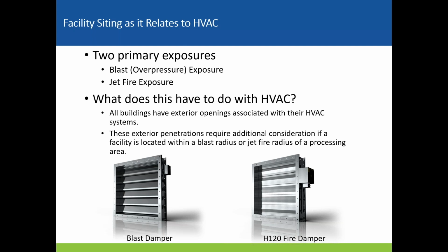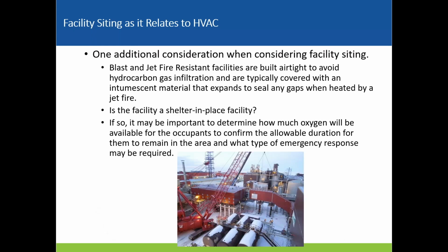So all buildings have exterior openings. And our blast dampers, and each has an H120 fire damper. So that's for a hydrocarbon fire for 120 minutes. That's theoretically what it's rated for. Not common, but very interesting.